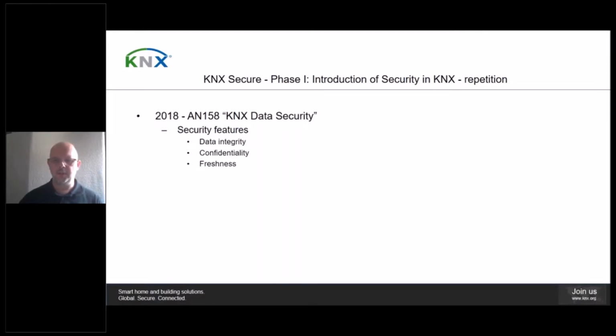Freshness. Freshness means protection against replay attacks. Every sender keeps an own sequence number for sending, which it increments with every message it sends out. This is stored by the receivers, and the next messages will by the receiver be compared with it, so it is not possible to replay the same message to the same receiver. KNX Data Security supports the following configuration modes: System Broadcast, Broadcast, Unicast, and Group Communication. Configuration is done secure by an out-of-band passing of an initial key, the so-called FDSK, which can be conveyed by a QR code. The communication on the bus for conveying the keys is encrypted as well.